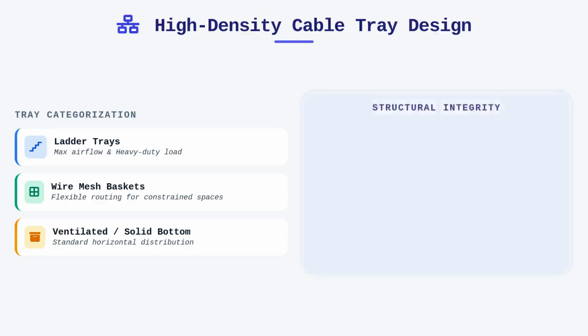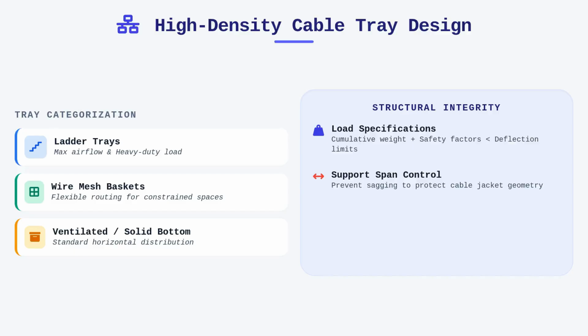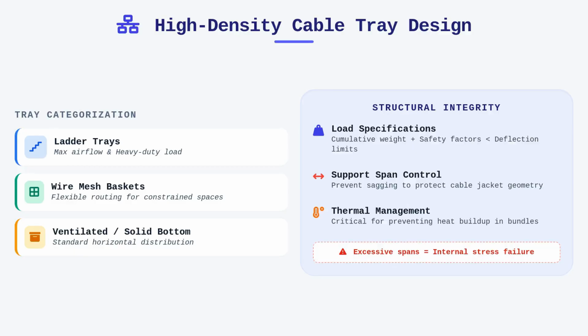Regardless of the type chosen, you must adhere to strict structural load specifications, ensuring that the tray can support the cumulative weight of the cables plus the necessary safety factors without exceeding the manufacturer's deflection limits. The distance between supports is a critical variable, as excessive span lengths lead to sagging, which can cause detrimental stress on cable jackets and internal geometry.